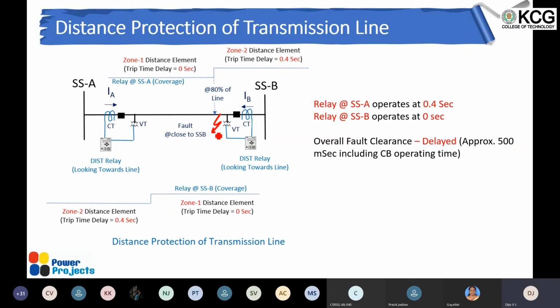Someone can ask why we are not covering 100% of the line in zone 1 itself. Because in that case, even for a bus bar fault, or maybe a fault on a line going out from there, if it is very close, this breaker will trip. So we cannot go up to 100% of the line in zone 1. That will create a lot of other issues. So we need to limit it to 80% for the protection to operate properly.